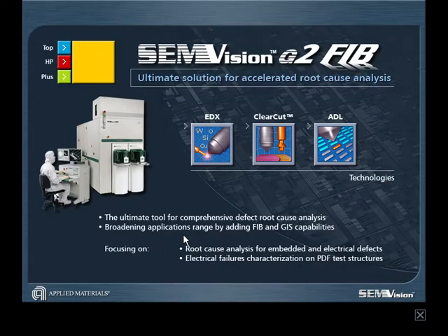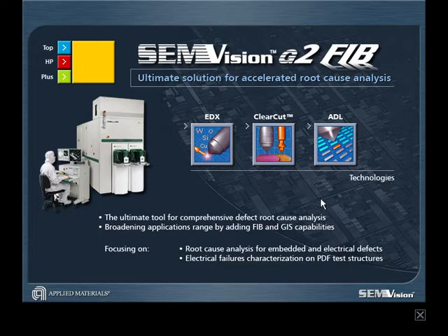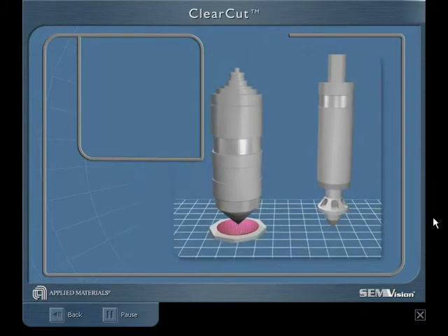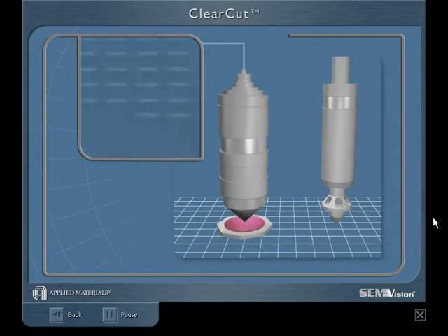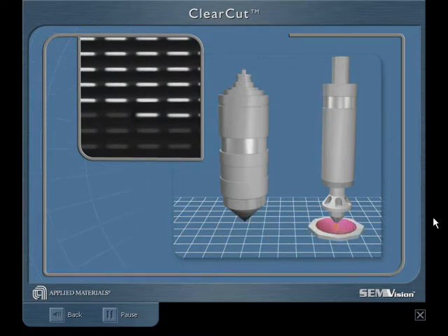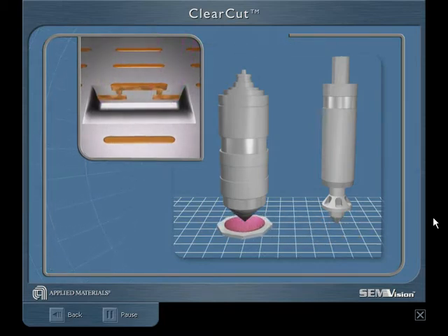At the top of the Semvision G2 product line, the G2 FIB is the tool of choice for extensive root cause analysis. The clear-cut technology comprises FIB and SEM columns that have been designed at optimal configuration. The wafer is positioned under SEM for review, then transfers at high accuracy to the FIB for milling and back to the SEM for profile imaging.